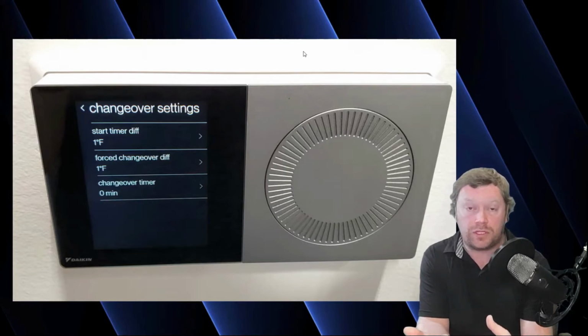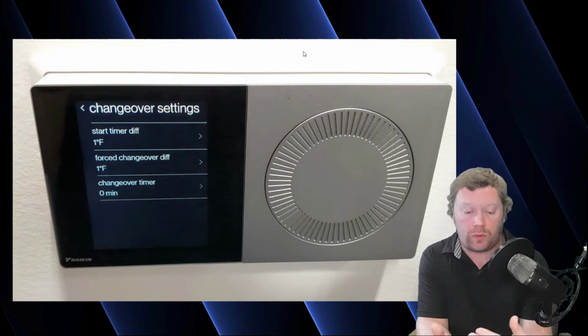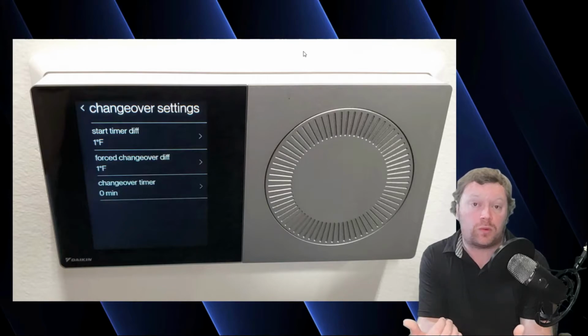Now, what your forced changeover differential will do is override that timer. So if the timer is sitting there ticking along internally because my room temperature has gone to 73 and my set point for cooling is 72, it waits and it waits until that timer expires to change. But if it gets 1 more degree above that set point, then that forced changeover differential overrides the timer and it will automatically switch modes.